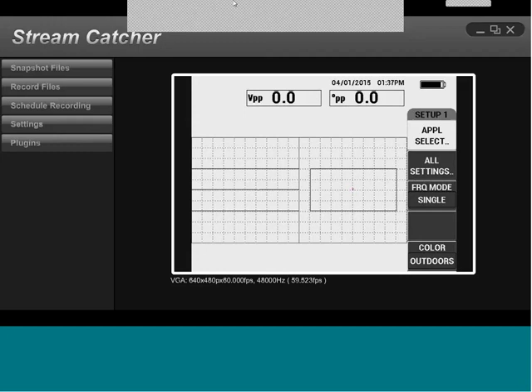I'm sorry, I need to go to the application section. I will again recall the bolt hole inspection just to default the system. I just press null, and I'm pretty much ready to calibrate on that steel. The difference with the steel is that we'll have to employ less gain. So let's lower the gain already. Then I'll adjust the angle the same way, so the lift-off goes to the right, or 180 degrees. And then I should be able to adjust that signal.